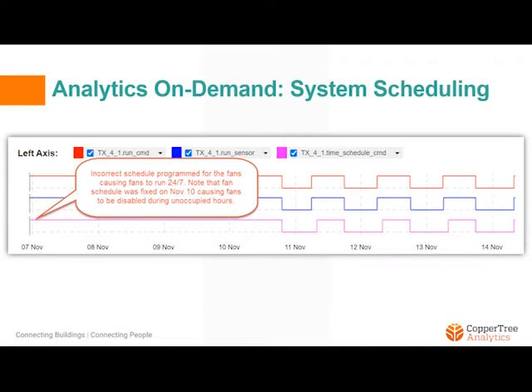So here's an example from a real site of an incorrect schedule programmed for a fan, causing it to run 24/7. When we look at our TL viewer, you'll notice that prior to November 10th, the fan was scheduled to run 24/7. That's our pink line, which represents the time schedule command for this particular fan. The red and blue lines represent our fan command and fan status. The rules applied within Kaizen will detect these anomalies and bring them to our attention so that corrective action can be done. You can see in this example that the proper time of day schedule was applied on November 11th, and thereafter the fan command and status points began to cycle on and off.